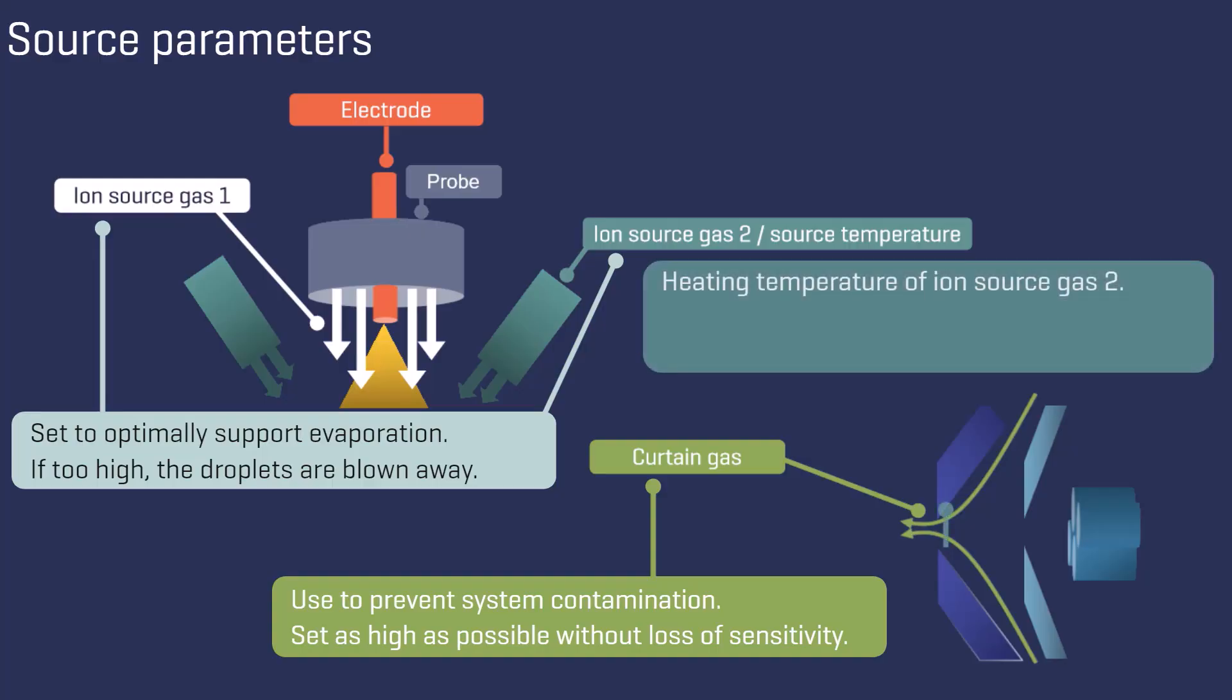The source temperature defines the temperature with which ion source gas 2 is heated. Ultimately, the entire source will reach this temperature. The heat also facilitates the evaporation of droplets.